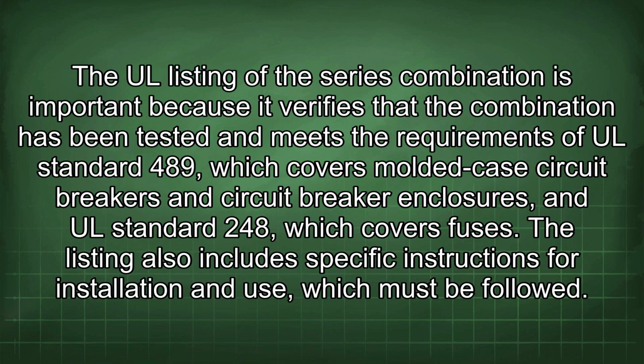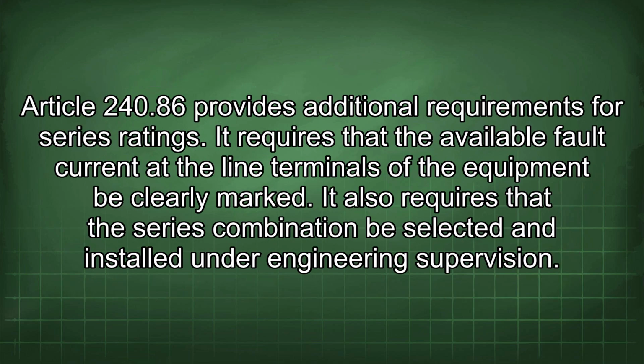The UL listing of the series combination is important because it verifies that the combination has been tested and meets the requirements of UL Standard 489, which covers molded case circuit breakers and circuit breaker enclosures, and UL Standard 248, which covers fuses. The listing also includes specific instructions for installation and use, which must be followed. Article 240.86 provides additional requirements for series ratings.